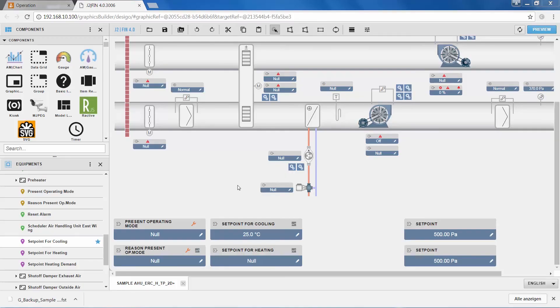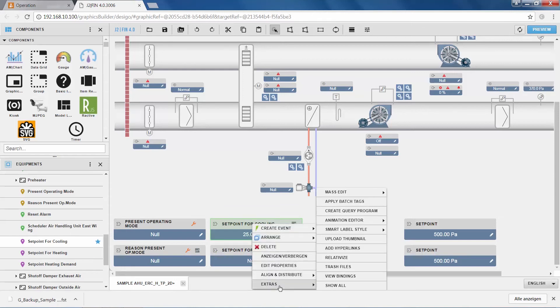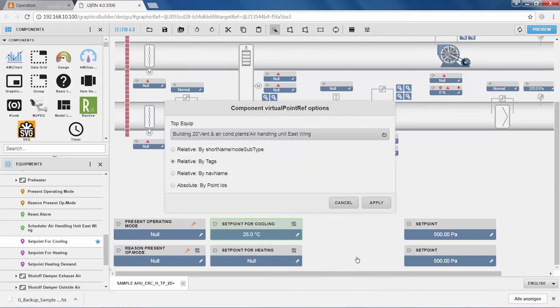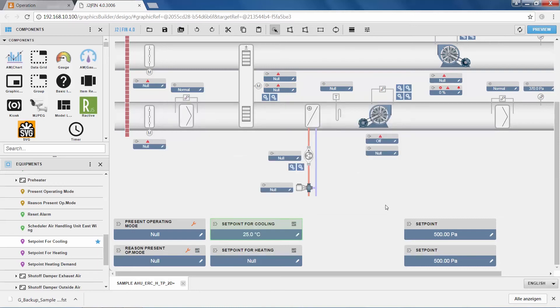Basically, wherever we open this graphic, it will always show the value of the east wing air handling unit's cooling set point. So what we have to do is make this binding more general. The control point offers us the possibility to create a relativized binding. In order to do this, we right-click the label for the set point for cooling, go to Extras in the context menu, and hit Relativize, upon which we get a dialog where we can choose to relativize by tags and relativize to the air handling unit of the east wing. We hit Apply, upon which the binding is set up in a relativized manner, and the only thing left is to hit Save.